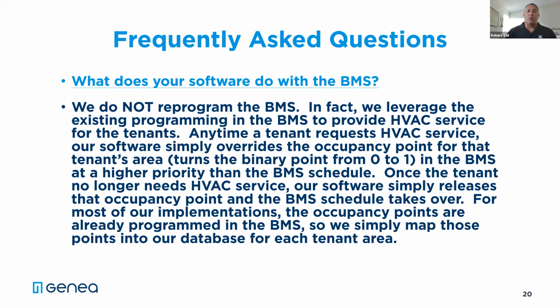We get a lot of this question: what does our software do to the BMS? One, we don't change anything in your automation system. We're not changing overall schedules or set points. What we're doing is leveraging the program that's already been done. Our system is simple, on-off. When somebody makes a request, we do a binary point to command service to turn on. Your BMS is then programmed to turn on all the appropriate equipment - the fan, the air handler, ultimately ramping up the chillers. Your BMS is already pre-programmed to do that. We're just going to leverage what's already done. That's why it's really easy to roll this out to buildings and take advantage of going on demand, because we can leverage all the pre-programming that's already happened at the site to make this advantageous for you and for your tenants.